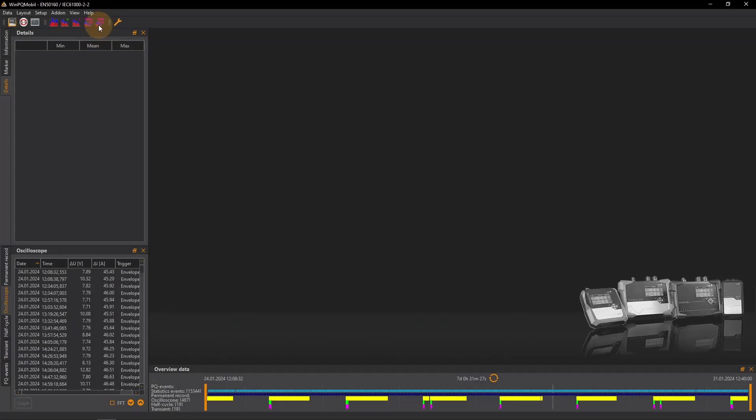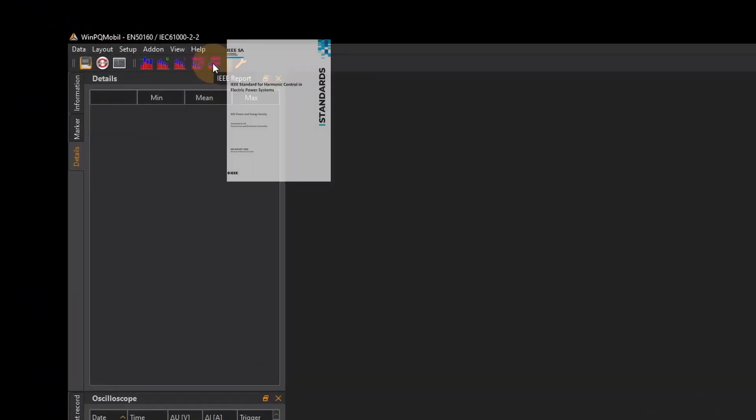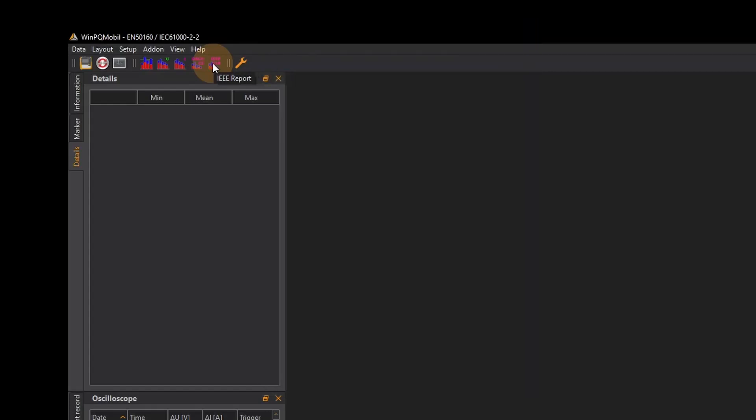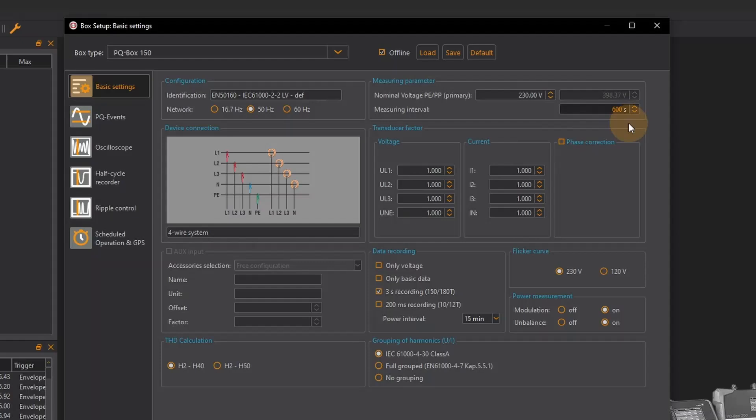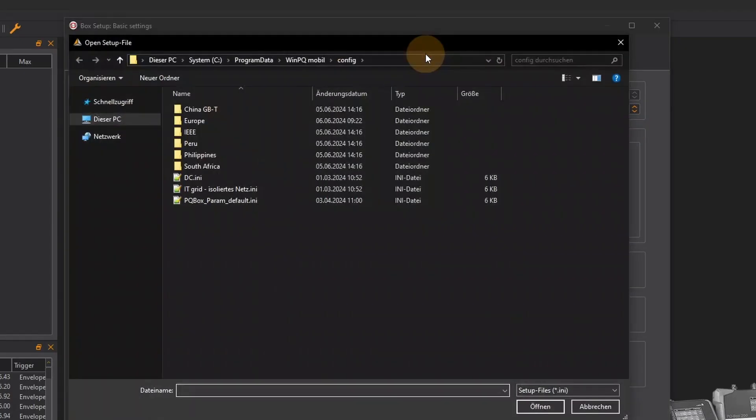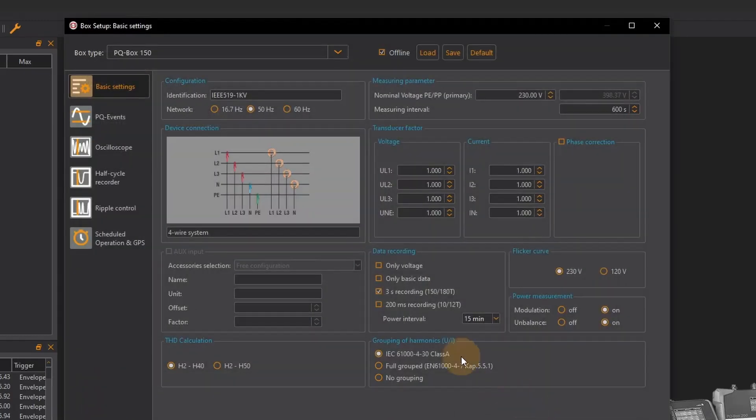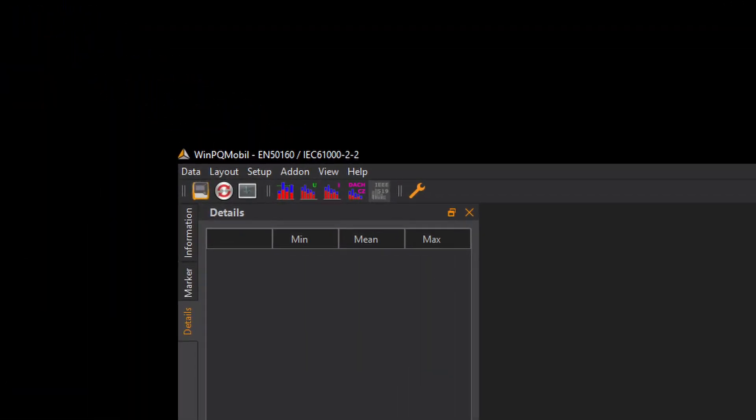For a report in accordance with IEEE 519 it is important that two crucial parameters are set correctly in the configuration of the PQ box before the measurement begins. Firstly, the report requires the 3 second data and secondly the measuring interval must be set to 600 seconds. When I load the corresponding configuration in WinPQ Mobile these parameters are already preset. If my measurement data meets these criteria the corresponding icon for the evaluation according to IEEE 519 is active.